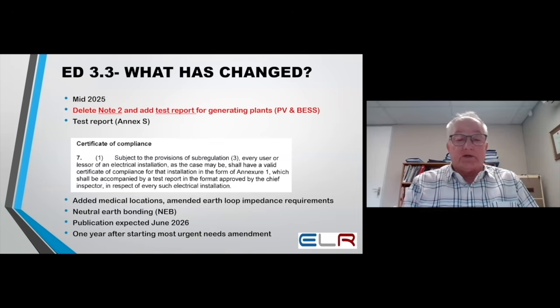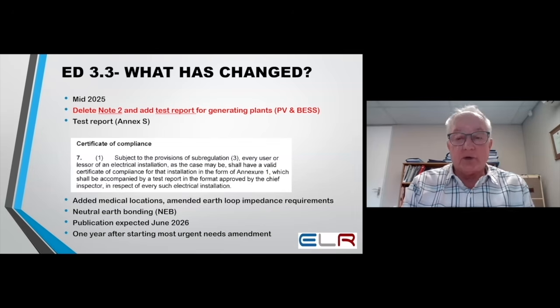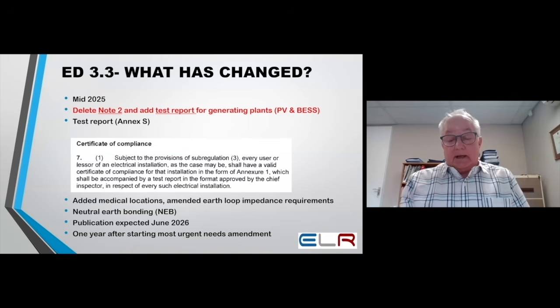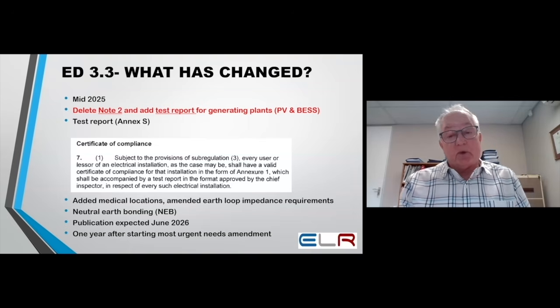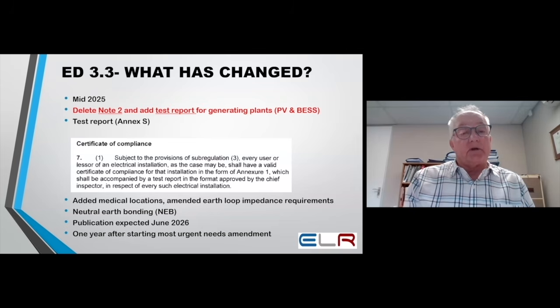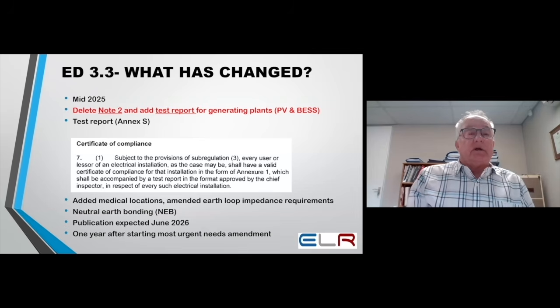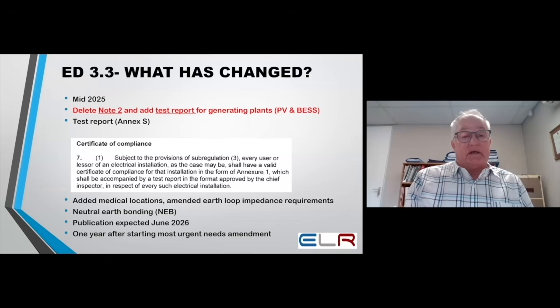So in mid 2025, keep in mind the duty to bring PV and solar into the wiring code was handed to us mid 2024. A year later, when I looked at the progress, and we met every month, three times more than normal, the progress was not good enough. We decided, based on a proposal by one of the members, that we would do an amendment only to get rid of note 2, clarify it, and add a test report specifically for PV and BESS.